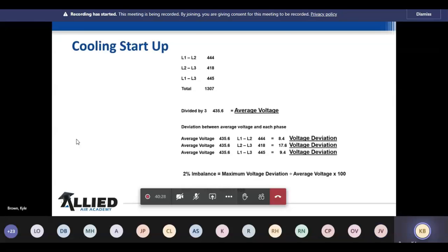But we're going to talk about voltage deviation, and then we're going to talk about amperage deviation and why this is important, because you can't have more than a 2% out of balance. And this is an example I always give. So we've got our voltages here. We checked L1 to L2, L2 to L3, L1 to L3, and we total that voltage up.